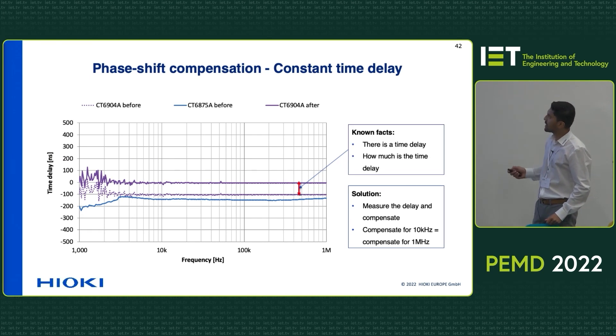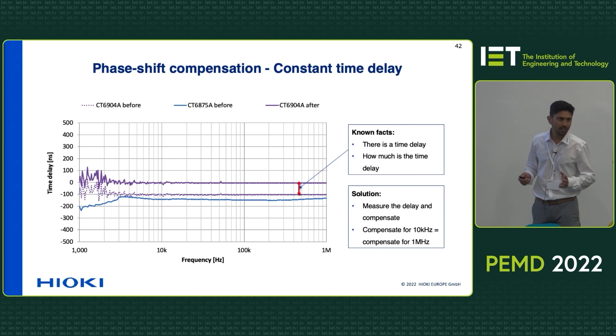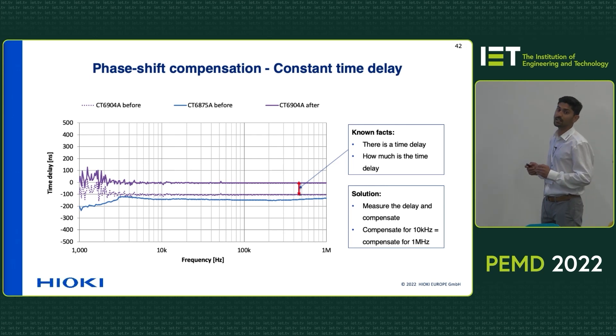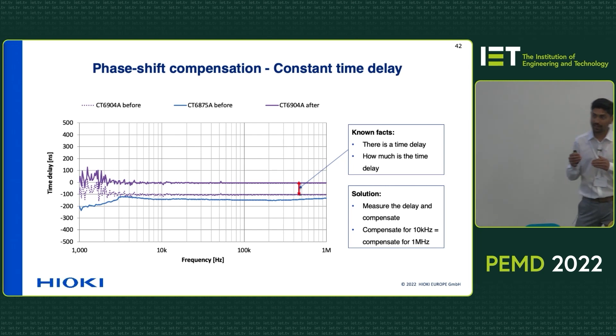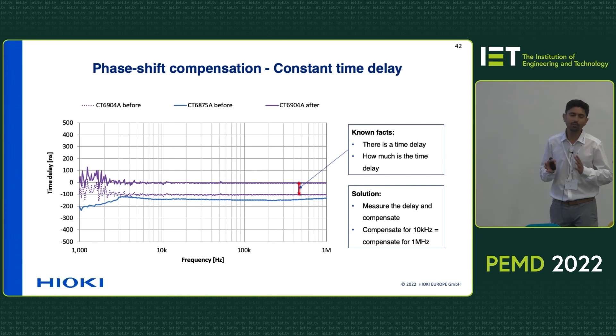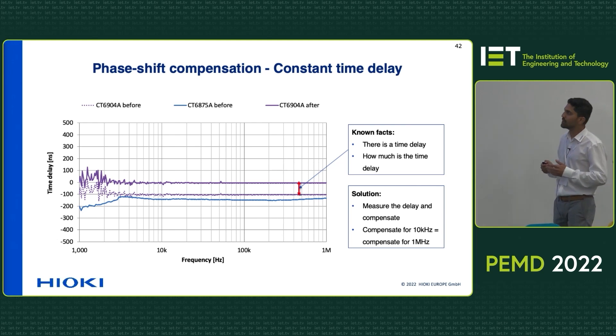If you do the same compensation in a current sensor where the delay is constant, it's not a problem. You can compensate the delay at 10 kilohertz, 20 kilohertz, 100 kilohertz, or one megahertz — it doesn't matter. By compensating at one frequency, you are effectively compensating for the delay across the entire frequency spectrum. At lower frequencies where the cycling time is in the range of milliseconds, an additional error of nanoseconds is not going to make a big difference in the power measurement.